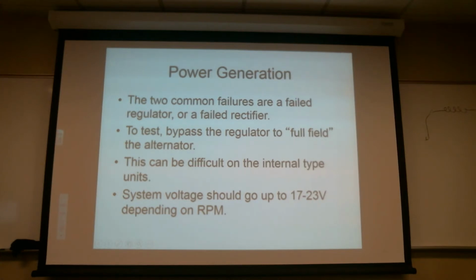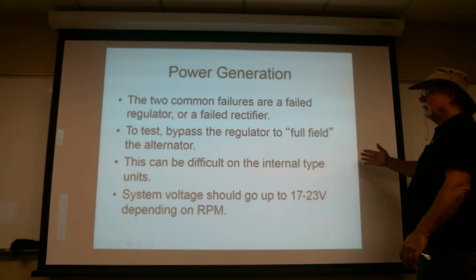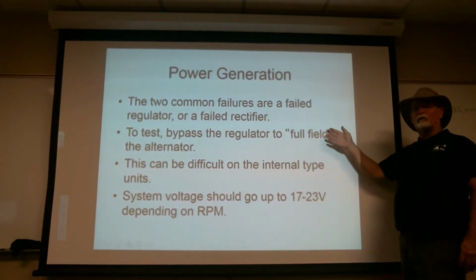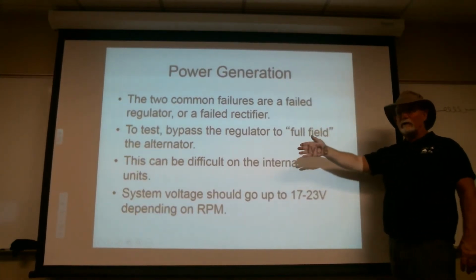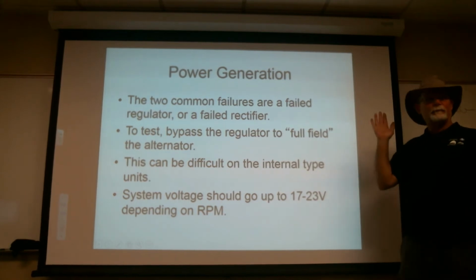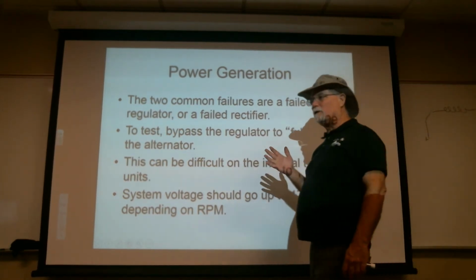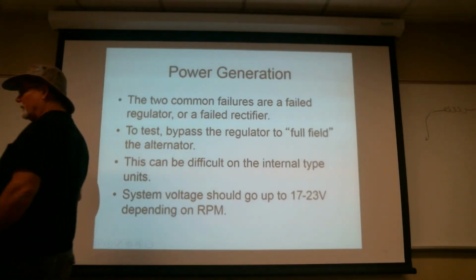Called full fielding the unit. It's not the same as flashing the field. Flashing the field is very different. That's only for commutator style. This we can do on anything. Full field it, and it tells us whether or not it was the generator or the voltage regulator. However, in all likelihood, you're going to be replacing both.